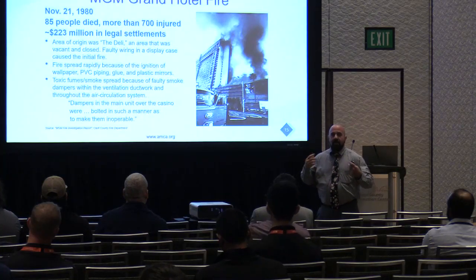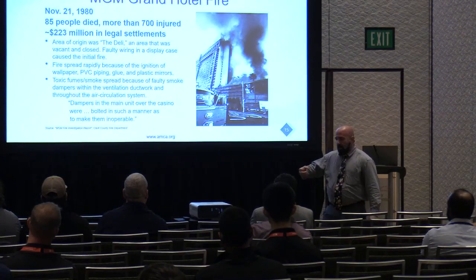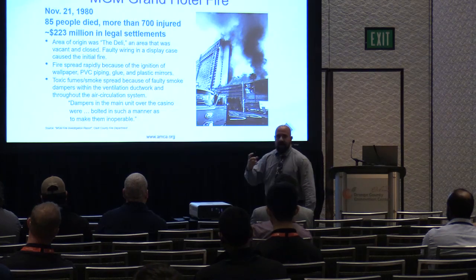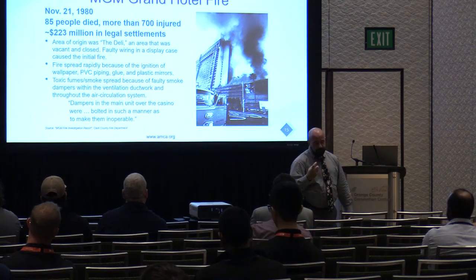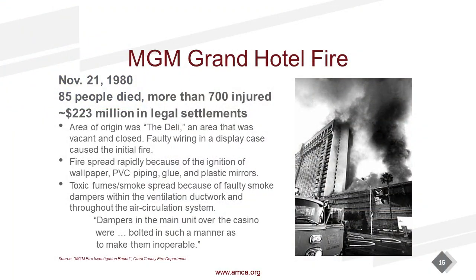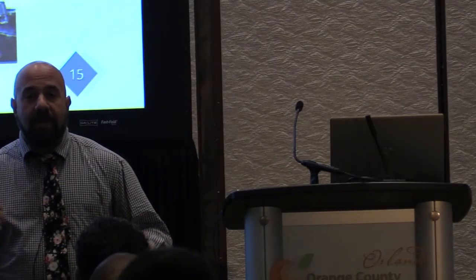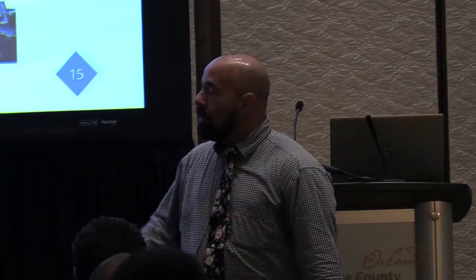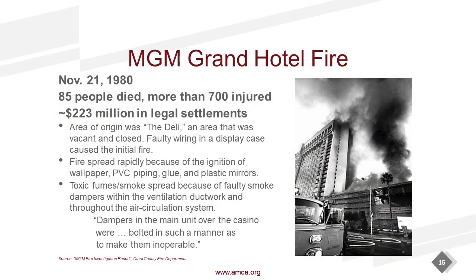If you remember the hair and the clothes, think of the building materials. All toxic smoke was created when that burned and melted. And unfortunately, that smoke spread through the HVAC system. The dampers in the main unit over the casino were found in a manner in which they couldn't close. They were bolted open. There was no code requiring the periodic inspection or the occupancy inspection of a fire damper or a smoke damper. We put them in, we set it and forget it, and unfortunately, this led to the smoke spreading through the towers.